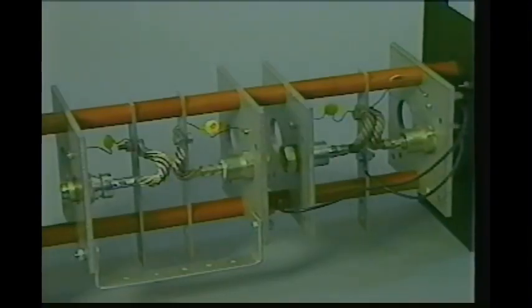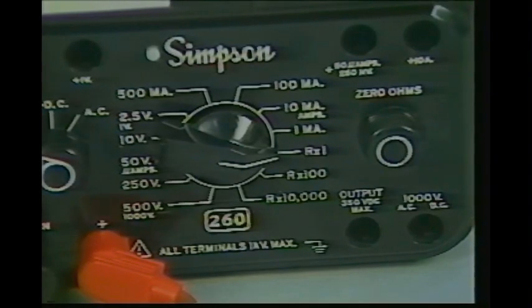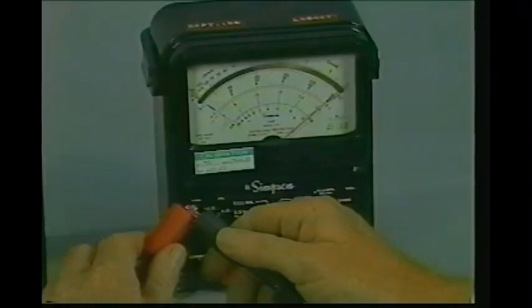After the diodes have been replaced, testing and repair of the rectifier is complete. In review, the first step is to open the primary power disconnect and ensure that the power is turned off. Second, select an analog meter with an R times one scale and zero the meter.